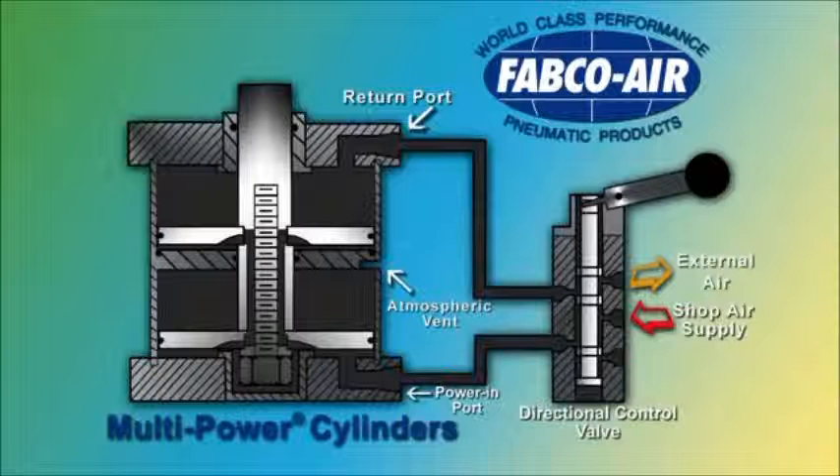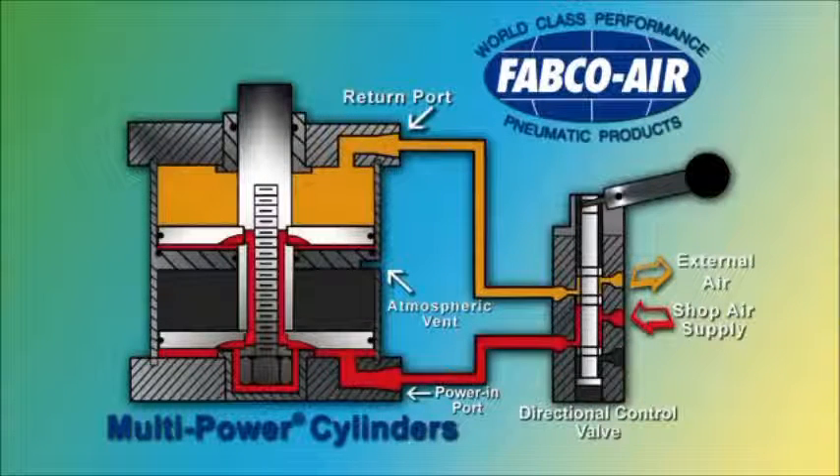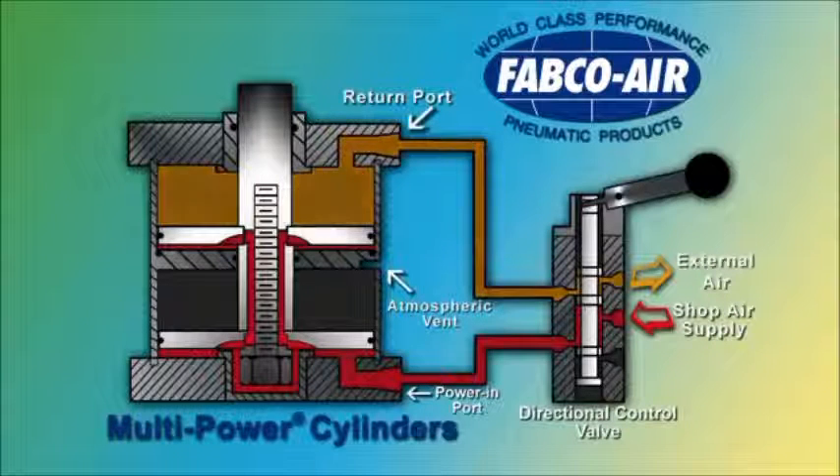Here we show a two-stage multi-power cylinder and a standard directional control valve. Shop air is directed through the directional control valve to the power-in port of the multi-power cylinder to the first piston, through the air slots and center shaft, and out through the second piston.